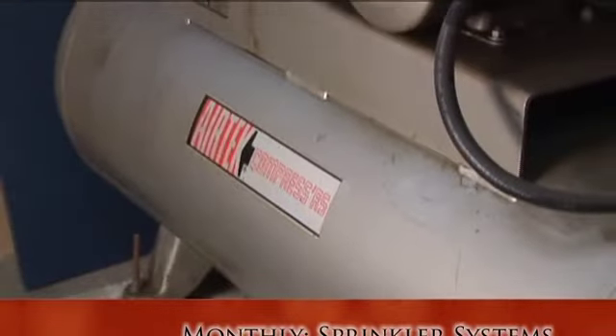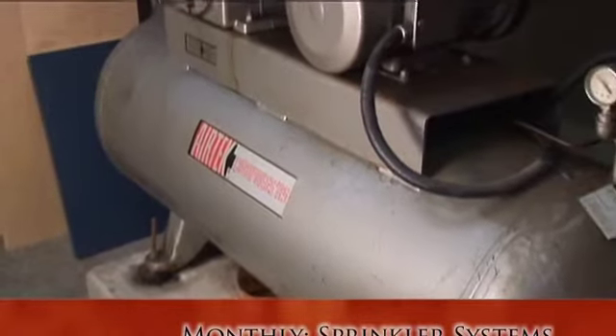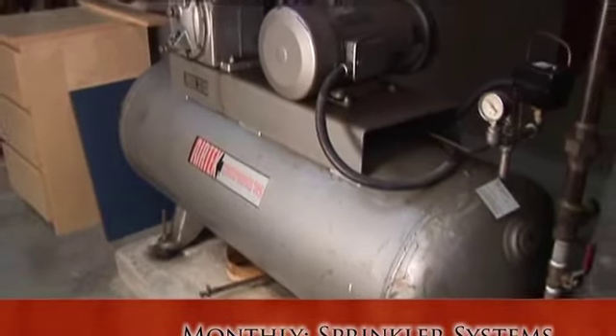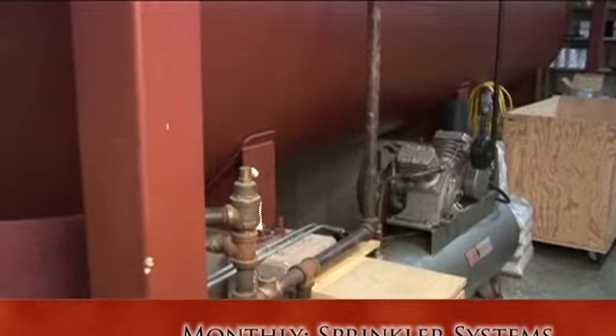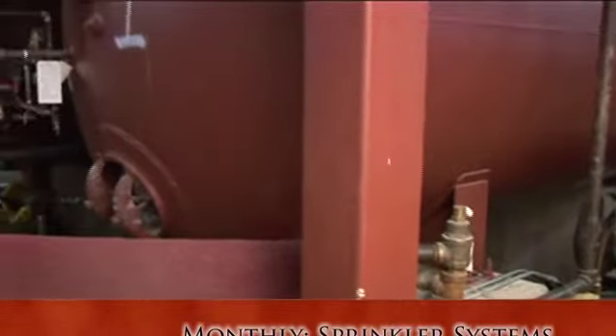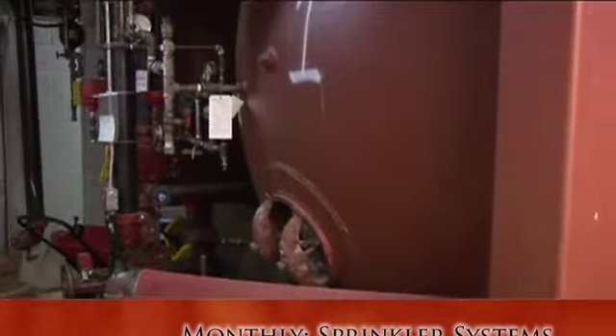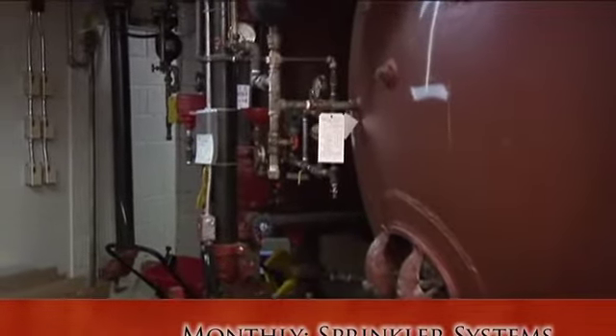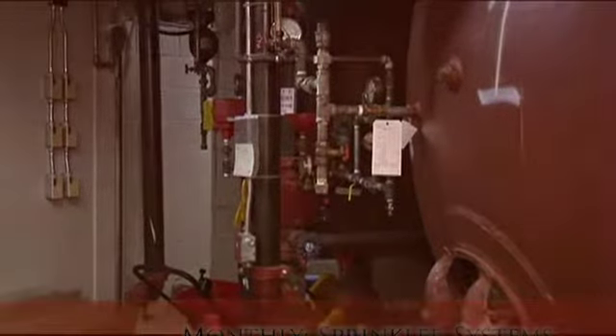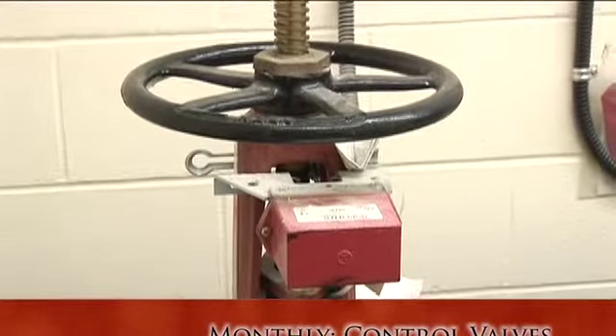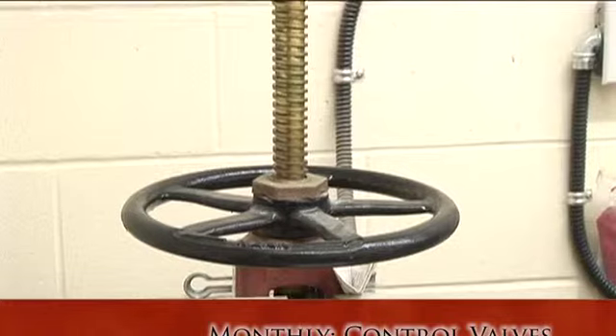The compressor for the dry pipe system is designed to maintain the air pressure in the pipes within a specified range. On occasion, the compressor will start and stop to ensure the pressure is at the correct level. If the compressor starts and stops continually or the pressure is below the recommended limits, advise your supervisor immediately. Hose cabinets should be inspected monthly to make sure that all the equipment is in place and in operable condition. Inspect all sprinkler system control valves which are locked open to confirm that they're in the fully open position.